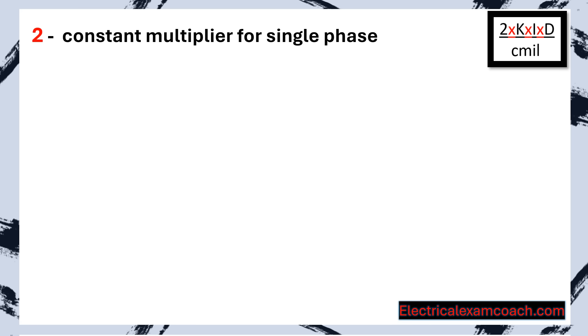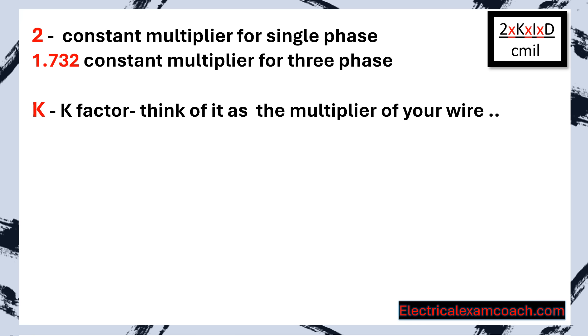2 is going to be our constant multiplier for single phase. If we're doing three phase, we're going to use 1.732 as our multiplier. K is going to be the K factor - think of it like a multiplier for your wire. For copper, it's 12.9 and aluminum, it's 21.2.